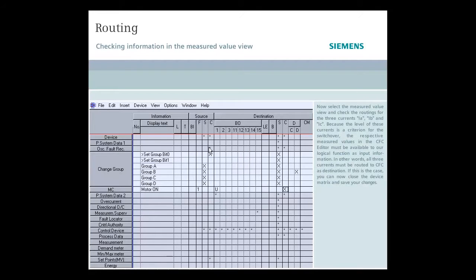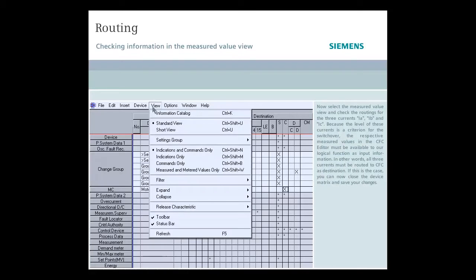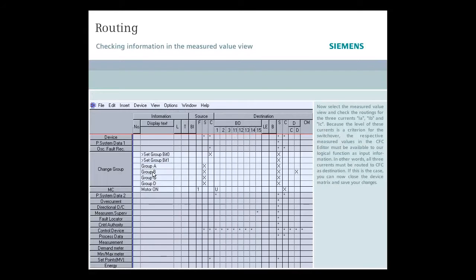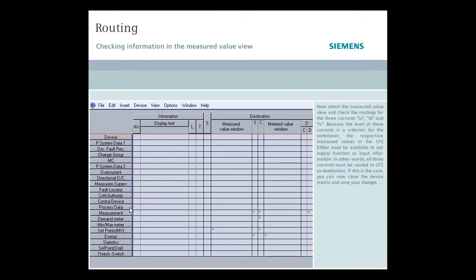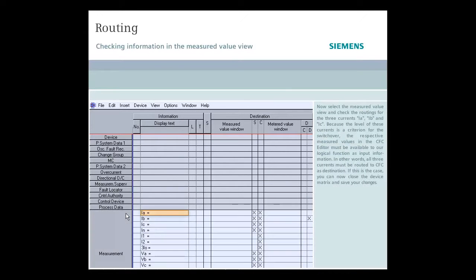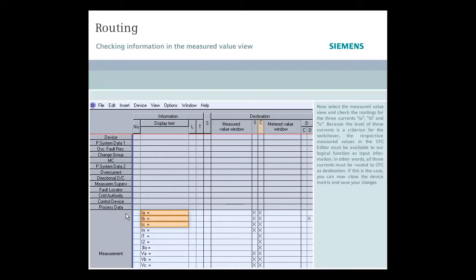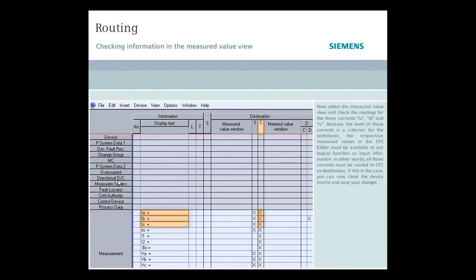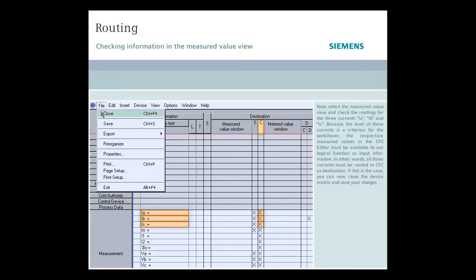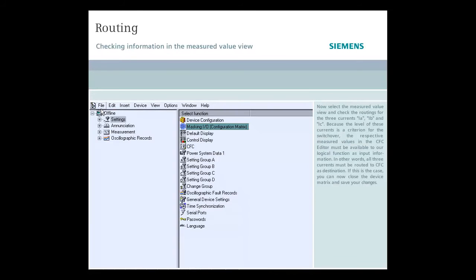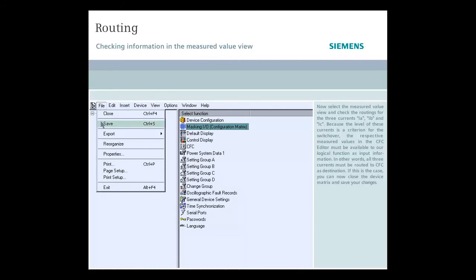Now select the measured value view and check the routings for the three currents IA, IB and IC. Because the level of these currents is a criterion for the switchover, the respective measured values in the CFC editor must be available to our logical function as input information. In other words, all three currents must be routed to CFC as destination. If this is the case, you can now close the device matrix and save your changes.